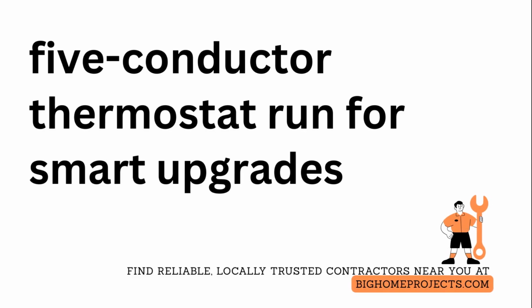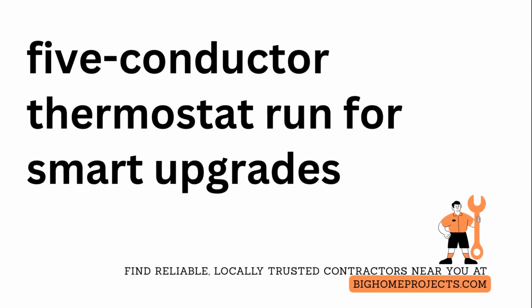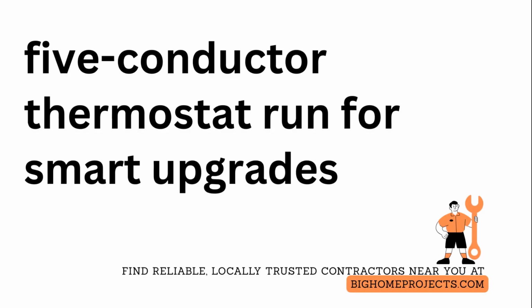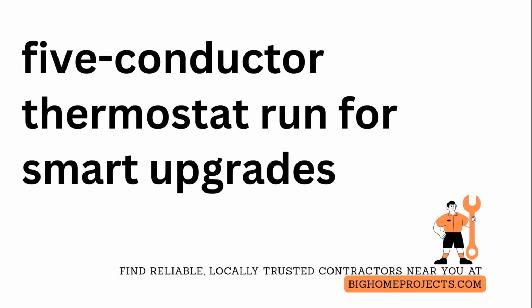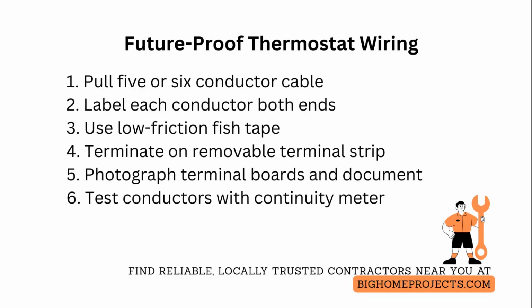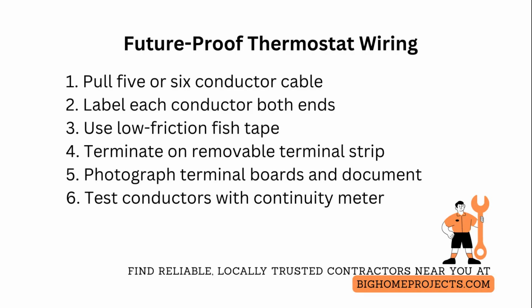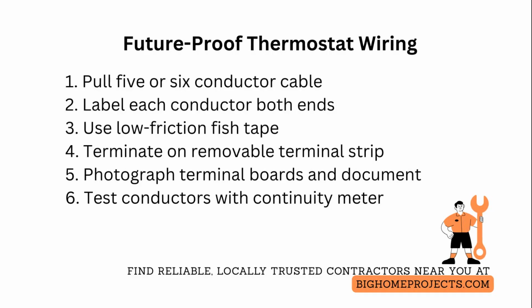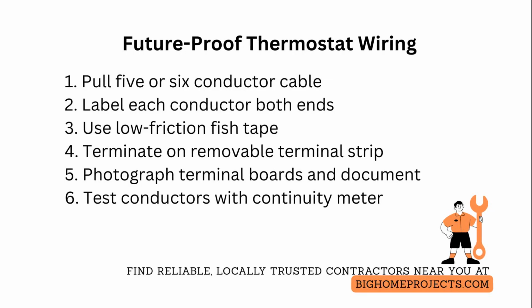Install extra thermostat conductors now to future-proof your system for smart thermostats, humidifiers, zoning, and easier troubleshooting. Most installers skip extra wires because the current thermostat works, but the expert move is to pull a 5 or 6 conductor cable, even if your present setup only uses 2. Run from the furnace or air handler to the thermostat location and label each conductor at both ends with durable tape and permanent marker so future devices can be wired without opening walls.